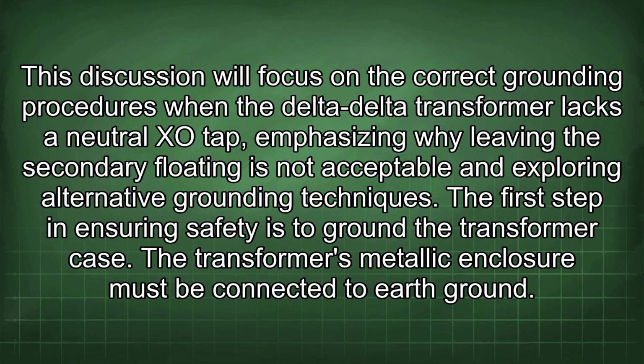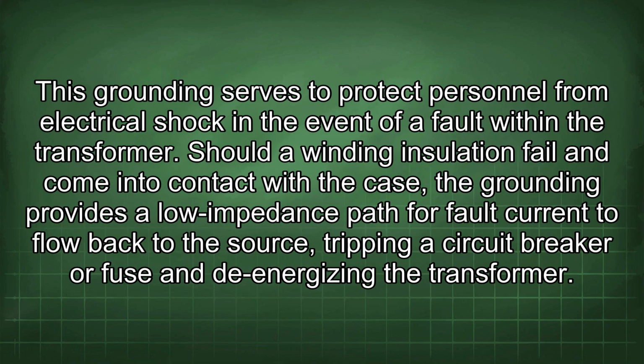The first step in ensuring safety is to ground the transformer case. The transformer's metallic enclosure must be connected to earth ground. This grounding serves to protect personnel from electrical shock in the event of a fault within the transformer. Should a winding insulation fail and come into contact with the case, the grounding provides a low impedance path for fault current to flow back to the source, tripping a circuit breaker or fuse and de-energizing the transformer.